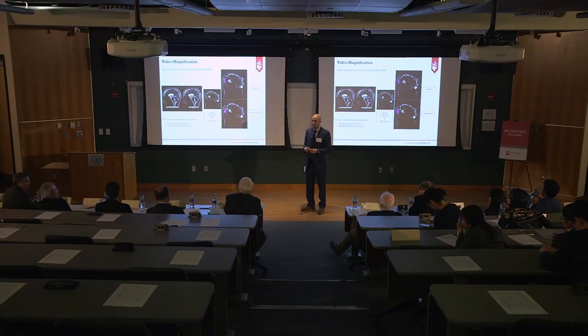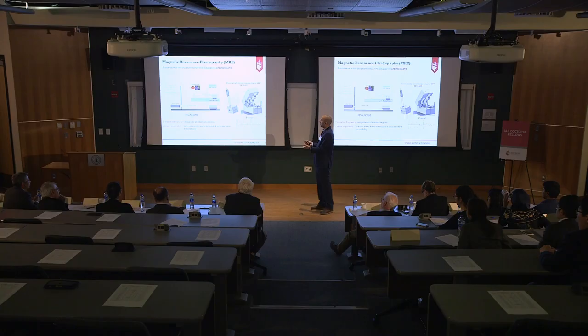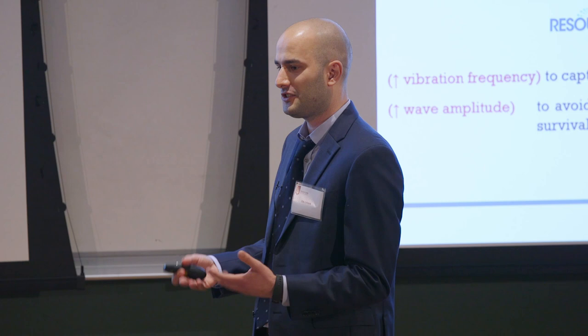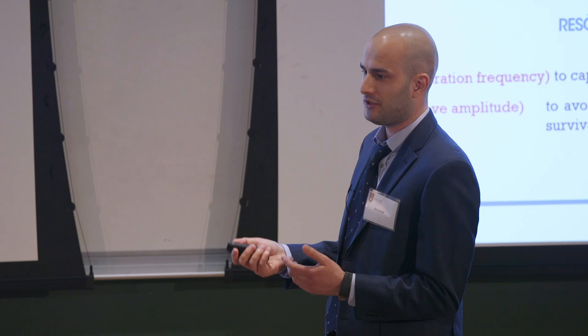Regarding the machinery shown: compressed air passes through holes and rotates a turbine. We have an opposed fiber optic probe, which is MR compatible since the entire setup must be positioned inside the MRI scanner. We use a gear reduction system at the tip of the shaft, which has an off-centered mass — analogous to throwing a brick inside a washing machine — generating centrifugal force and creating oscillation. We have submitted an invention disclosure about this.